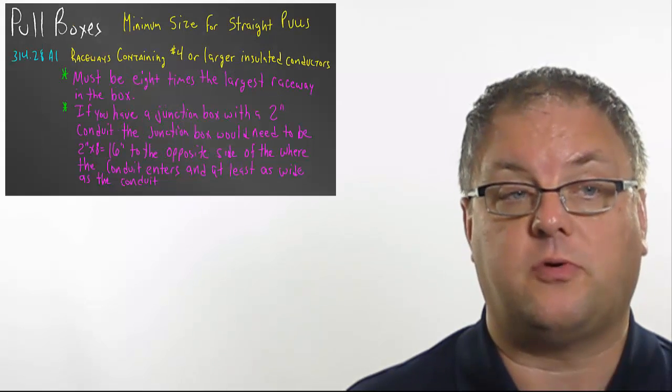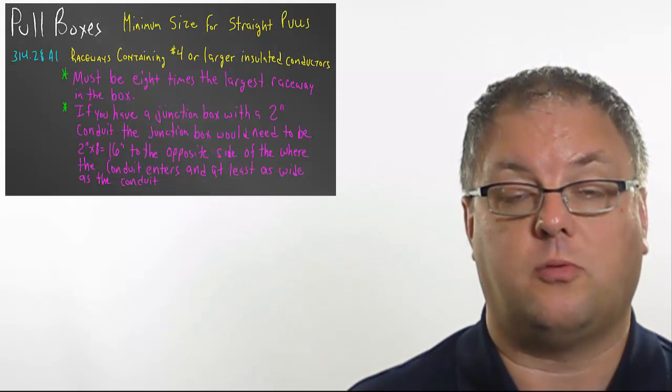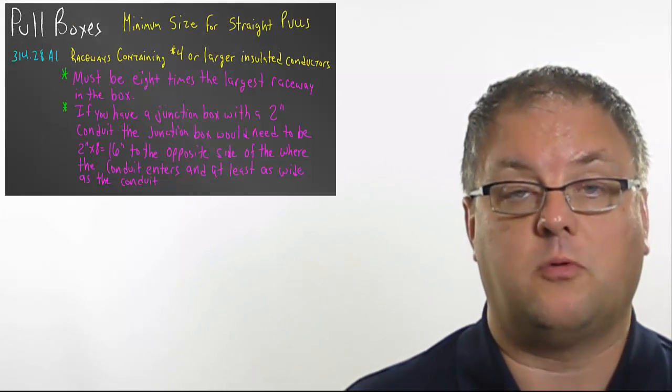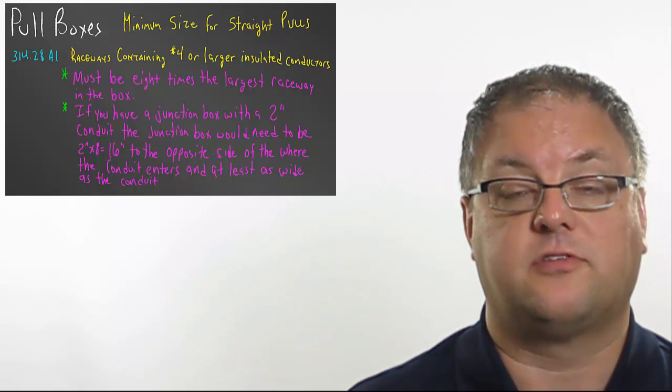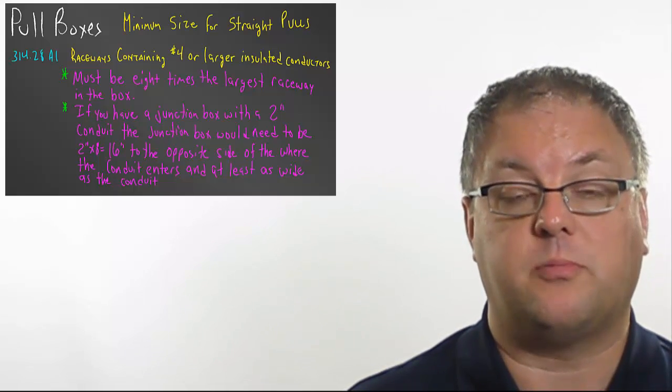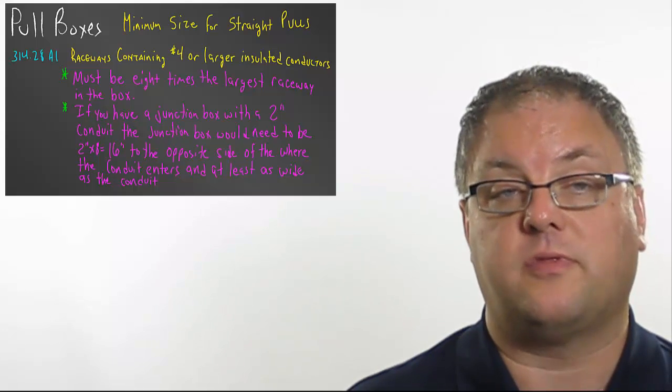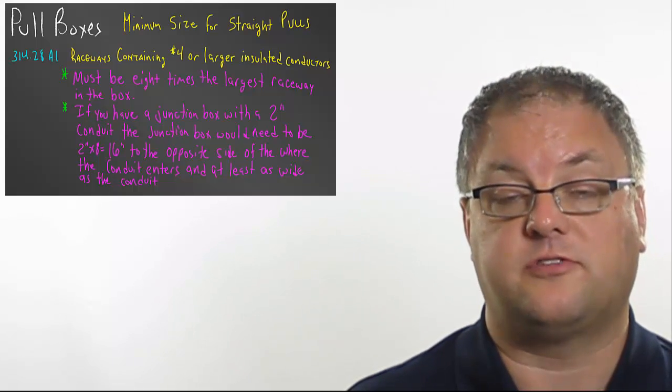Now, let's get on to our pull boxes. Well, I hope that you guys did good on those calculations. Why don't you try a couple on your own? Maybe use some real life scenarios that you've had at work and see how you do. If we get into article three fourteen twenty eight, we start to talk about pull boxes. And when we talk about sizing a pull box, we need to talk about straight pulls, and then boxes with angle, u-pulls, and splices in them.